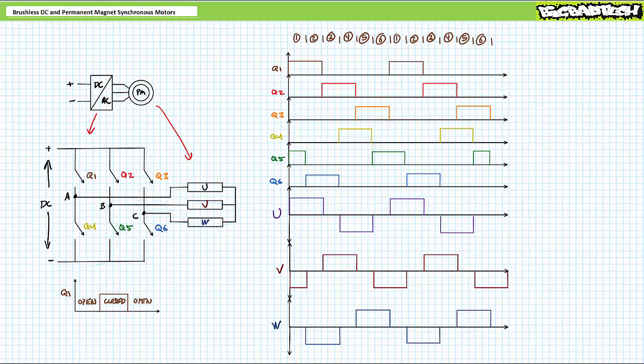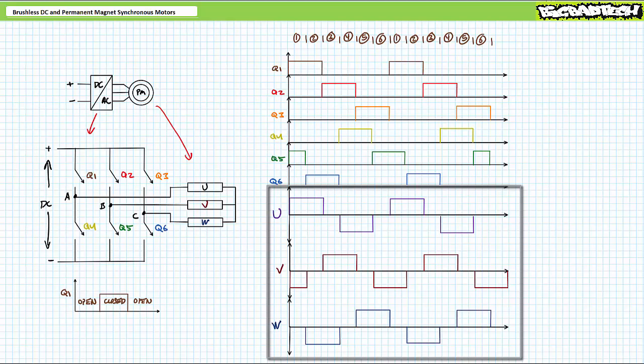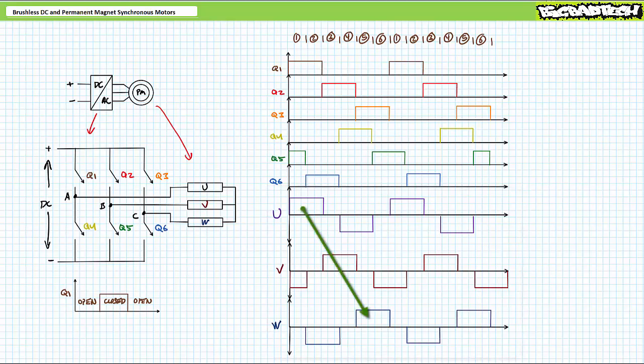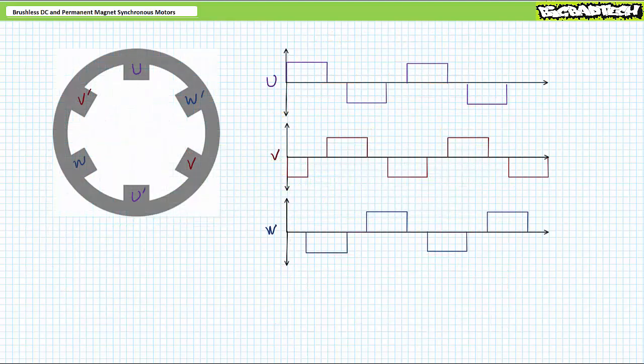The sequence then repeats itself. You will note the resultant polarity of outputs U and V oscillates, and they do so such that they are offset from one another by a relative 120 degrees. Three phases, six steps, with a 120-degree relative phase shift. For this reason, this control method is called three-phase six-step 120-degree modulation. Consider what happens when these waveforms are applied to a stator with one pole pair per phase physically displaced from one another by 120 degrees, or if you prefer, two poles per phase at 60-degree increments.